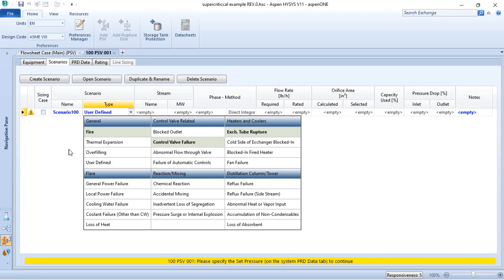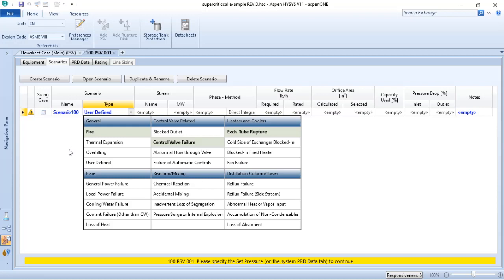Another scenario of overpressurization is a control valve failure. Most often, when dealing with pressure control, you want to decrease a high pressure to a low pressure and you need to consider the scenario of having this control valve full open. So what happens if you have a high pressure upstream of your control valve and it goes to downstream of your control valve?